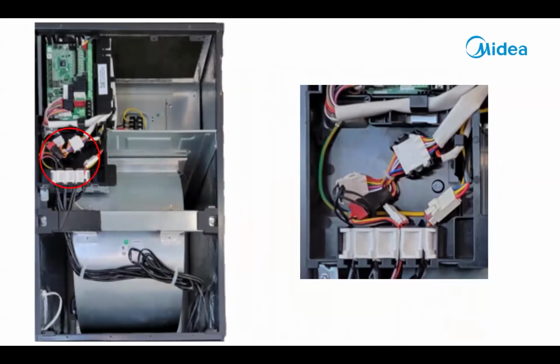All right, so here's a picture of the upper module. Notice in the red circle, those are the connectors for your blower motor, your sensors, and the EEV motor. Actually, your A2L sensor is connected there as well. In order to separate the modules or even pull the blower, you don't have to unwire anything from the board. You take those plugs apart, separate them, and then plug them back in when you're done. So there's no remembering how things were wired on the board or where the plugs went.